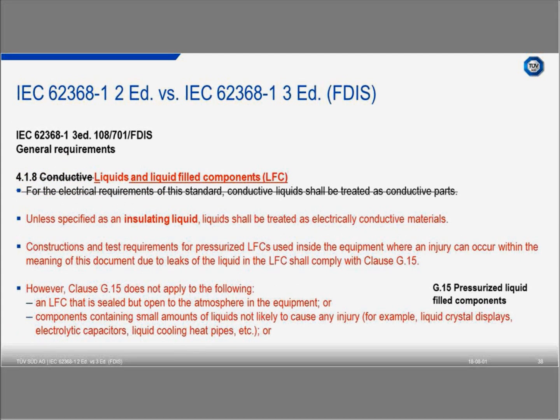Then there is the topic about liquid and liquid filled components, and a point about when these requirements are not applied. This is important: the requirement and also the test from Annex G are not applied if we have a liquid filled component that is sealed but open to the atmosphere, so there cannot be high pressure inside. This covers components that contain a small amount of liquid, for example liquid crystal displays, electrolytic capacitors, or cooling pipes for some reason.